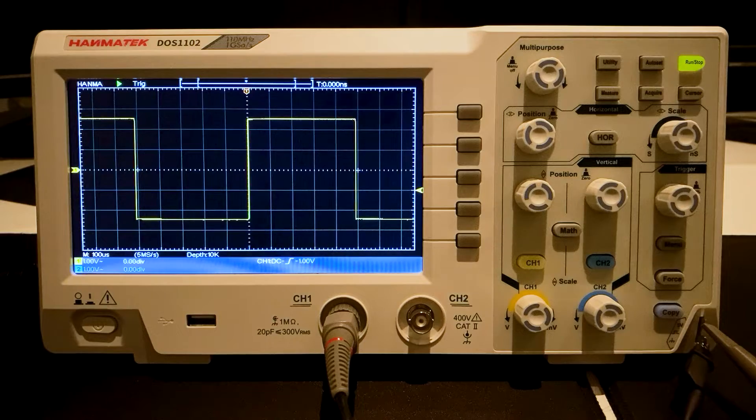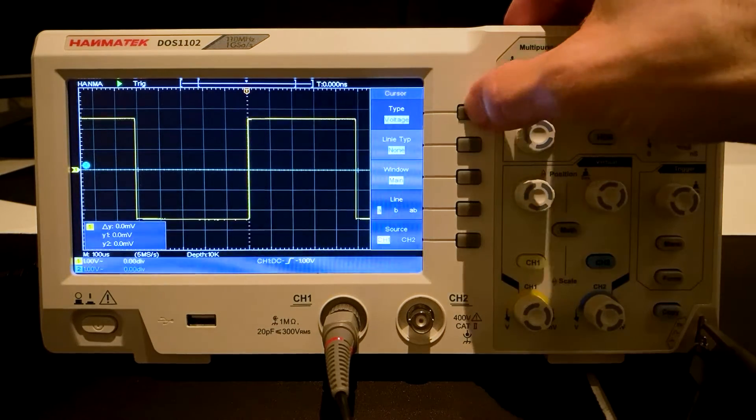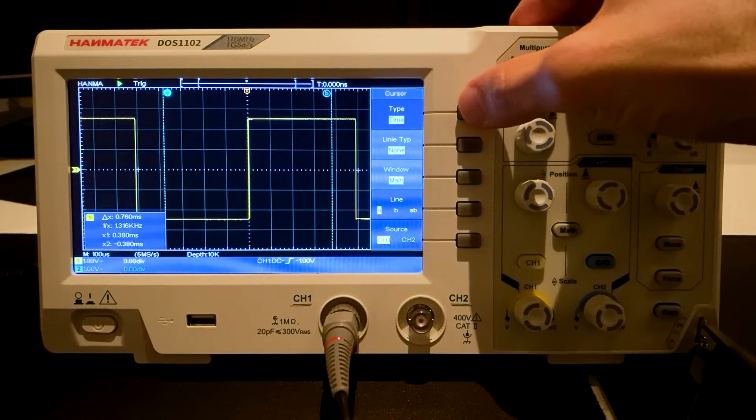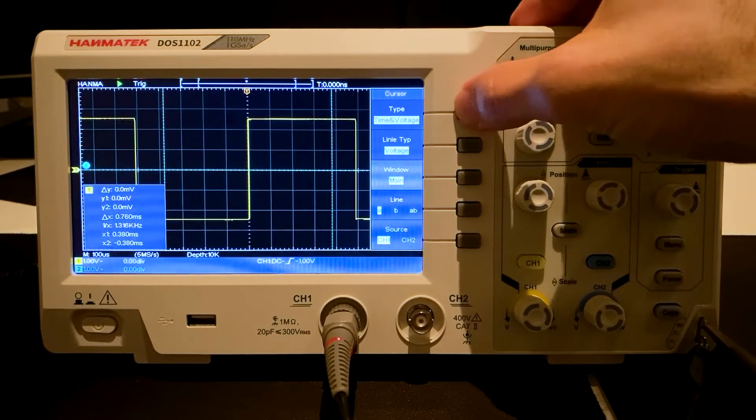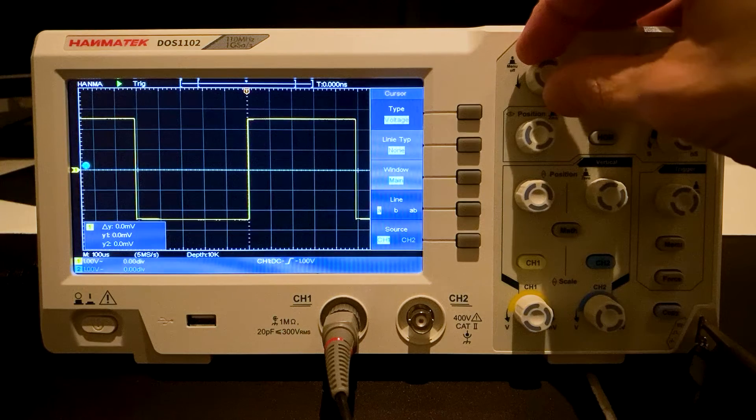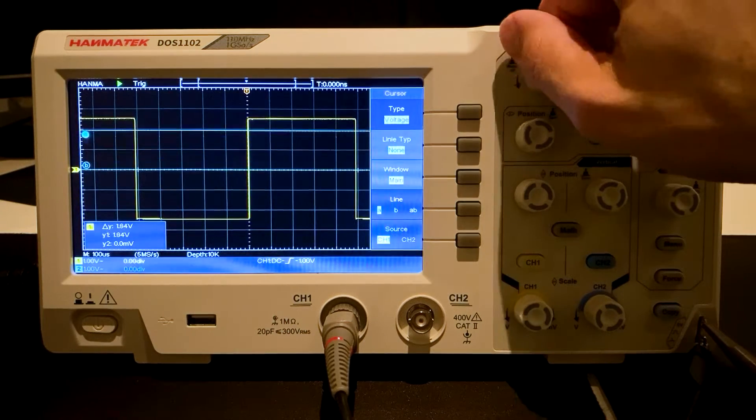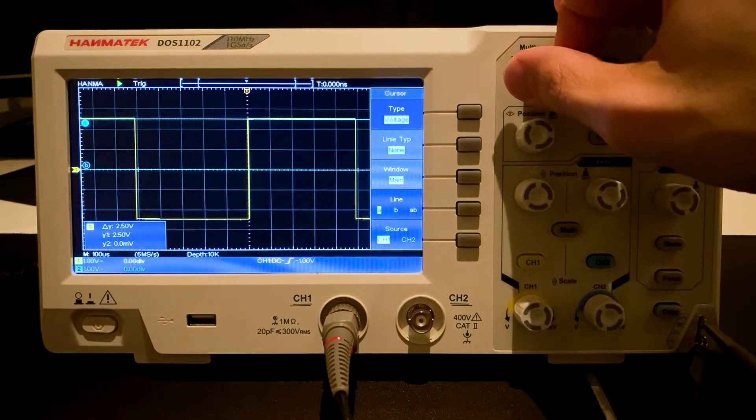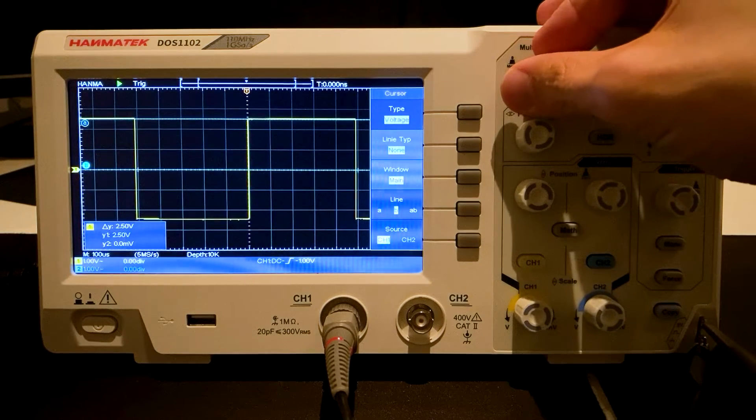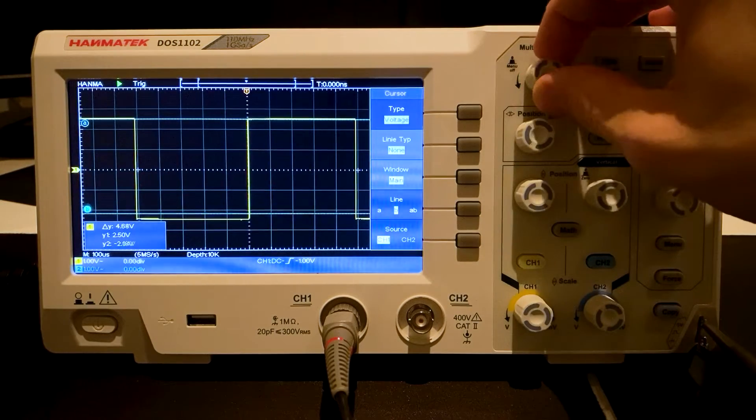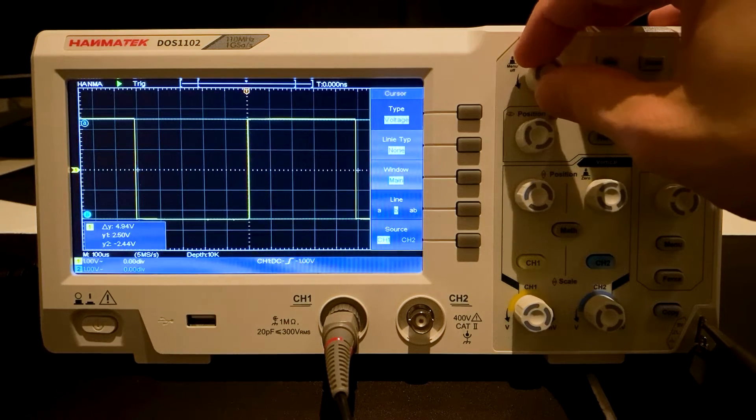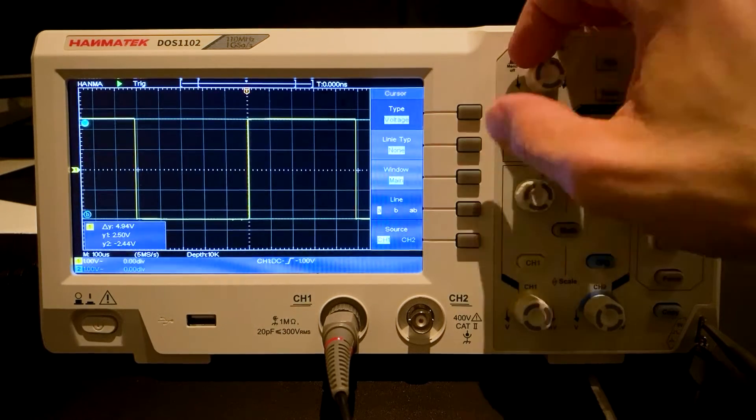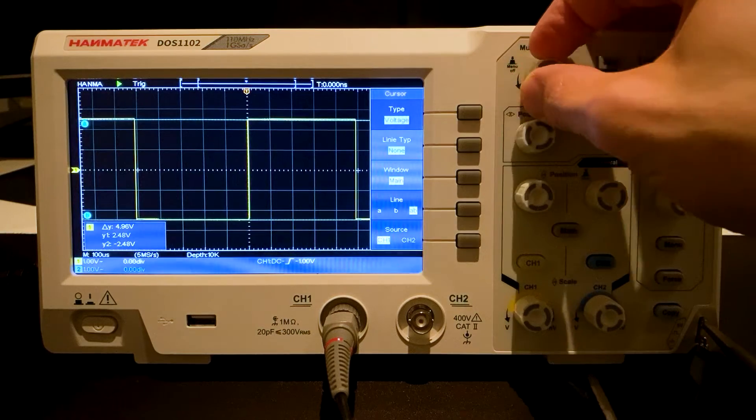The Cursor function is used to measure voltage and time. You can select Time, Time and Voltage, AutoCursor and Voltage again. The measurement lines can be changed with the Multipurpose knob. The change between the measuring lines takes place with the parameter Line. Line A selects the first, Line B the second and Line AB selects both lines. The result is displayed in the lower left box.